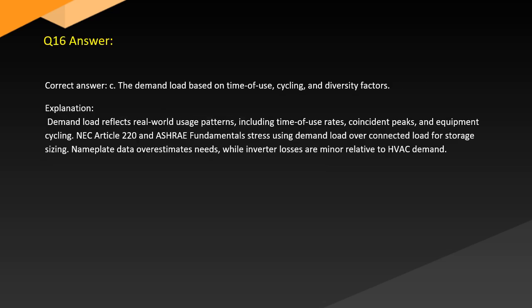Answer. Correct answer. C. The demand load based on time of use, cycling, and diversity factors. Explanation. Demand load reflects real-world usage patterns including time of use rates, coincident peaks, and equipment cycling. NEC Article 220 and ASHRAE Fundamentals stress using demand load over connected load for storage sizing. Nameplate data overestimates needs, while inverter losses are minor relative to HVAC demand.